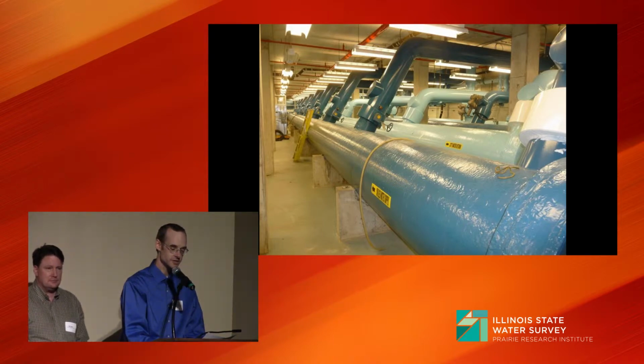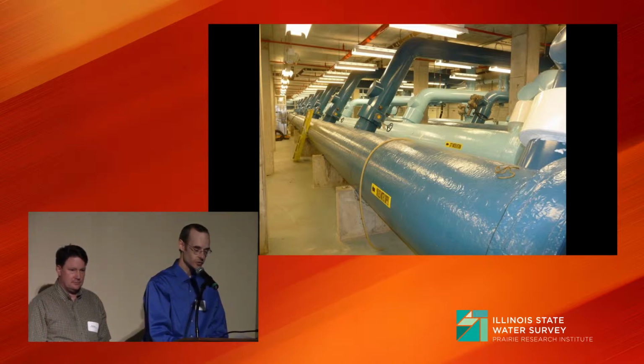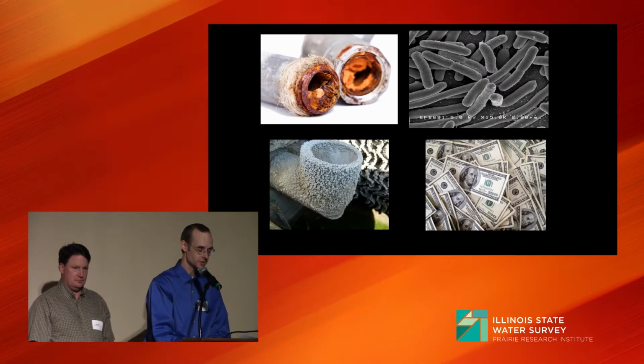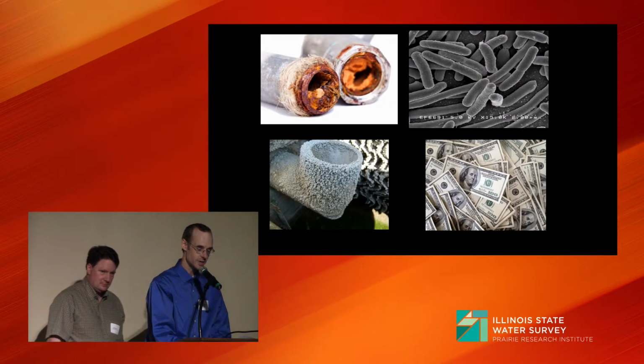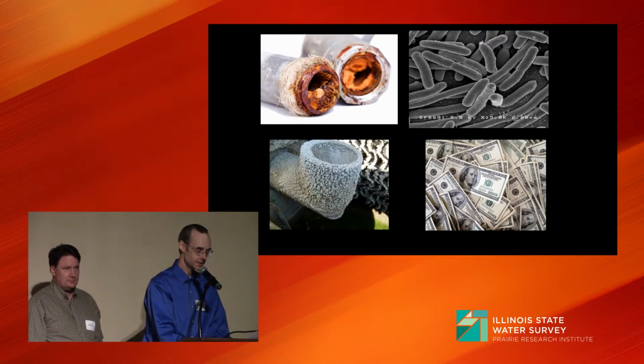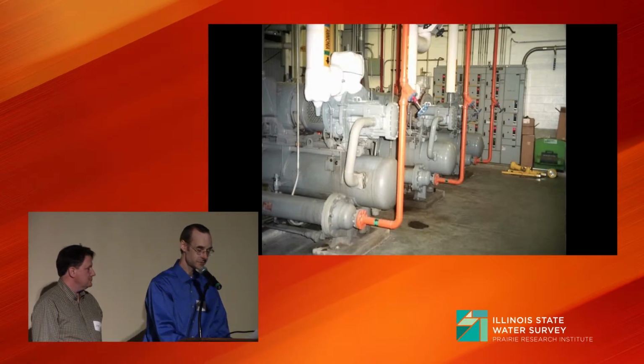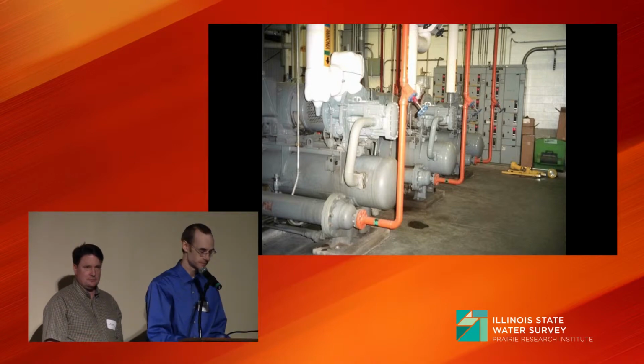For example, the air conditioning in this campus is provided by an underground loop circulating 10 million gallons of chilled water. We treat water in order to minimize corrosion, microbiological growth, and the formation of scale, or in other words, rust, bugs, and rocks. And in doing so, we save piles of money by extending service life and reducing energy costs. How much money? Typically, the investment in heating and cooling systems might be 10 to 15% of the cost of a building's construction. A rough estimate for the value of those systems on this campus might be $600 million. So any extension of service life adds up quickly.